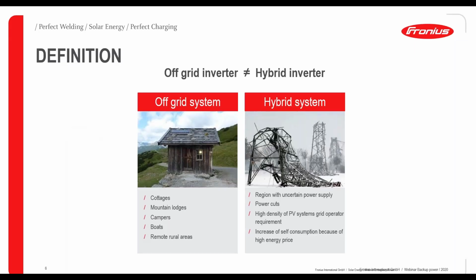Good. Some general information. I'd like to start with a basic definition of the hybrid inverter. The hybrid inverter is not an off-grid inverter. Our system is made for houses with a grid connection, but maybe in a region with an uncertain power supply, power cuts, and a high density of PV systems, for example. In this case, we use a hybrid inverter, so that the hybrid inverter should just cover the power cuts to give the customer power supply even in a short power cut.